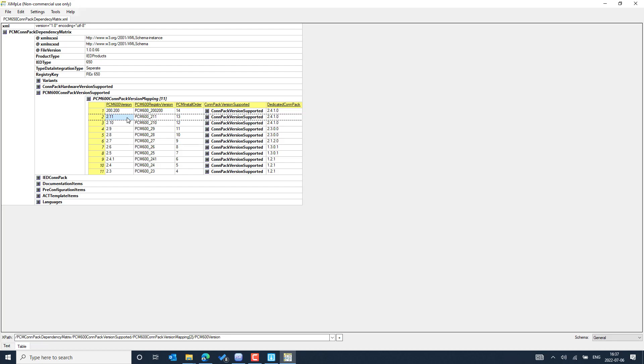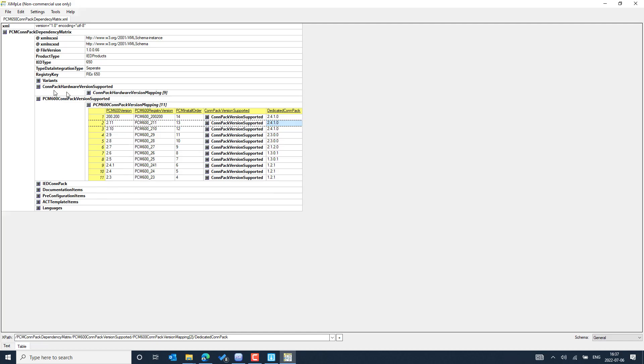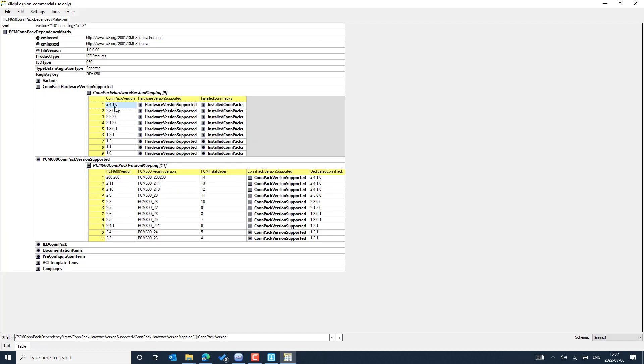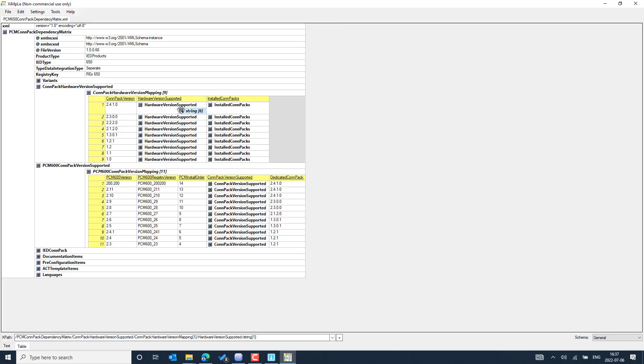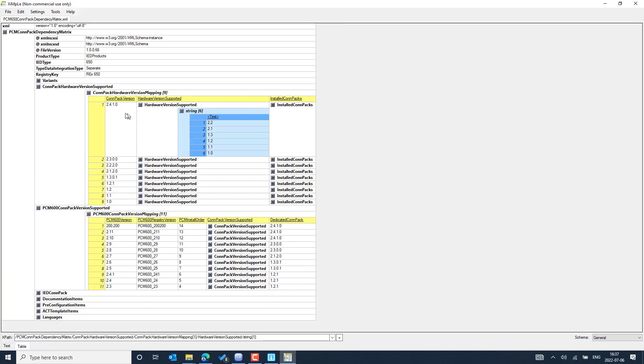In the table, you can see the recommended connectivity package version for PCM600 2.11 with the 650 series compact is 2.4.1.0. Under the compact hardware version supported, if you have installed the 2.4.1.0 compact for the 650 IED, you can expand hardware versions supported and see that it supports different IED hardware versions starting from 1.0, all the way through the latest 650 versions including 2.3 and 2.4. This is how you can easily understand compatibility with this tool.